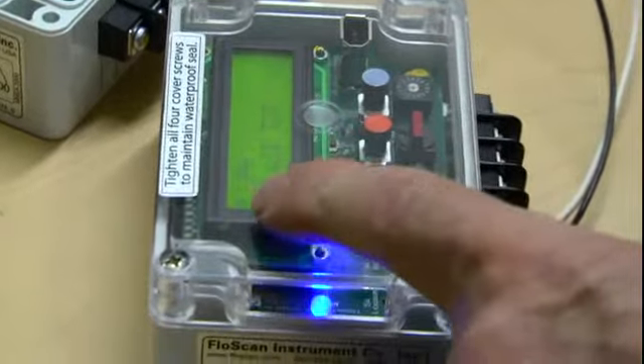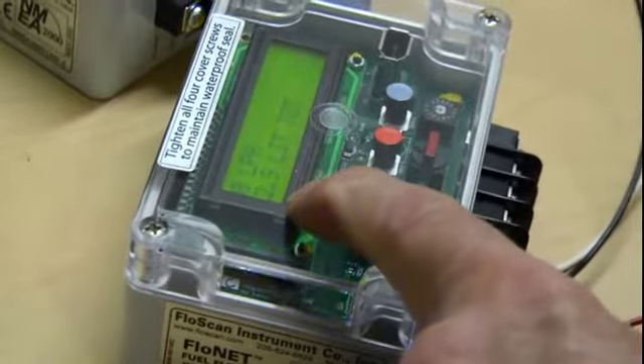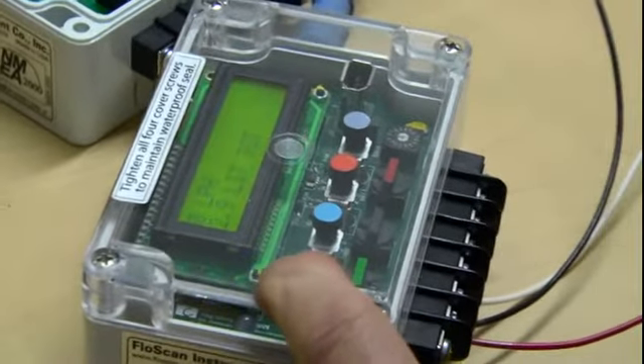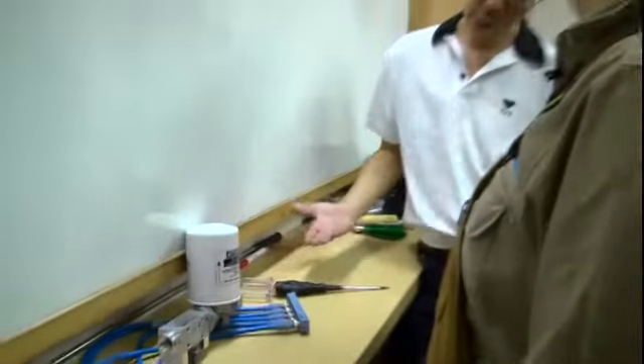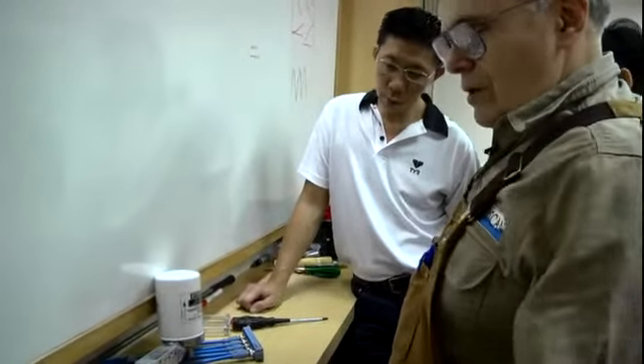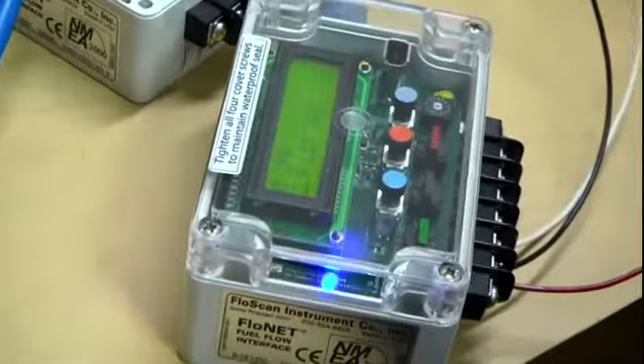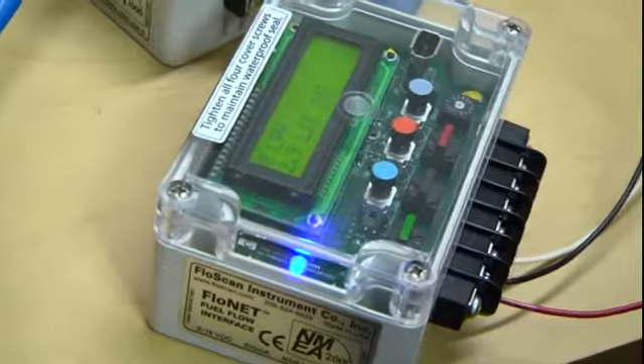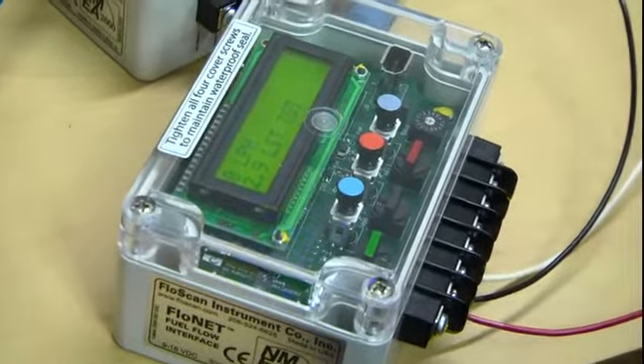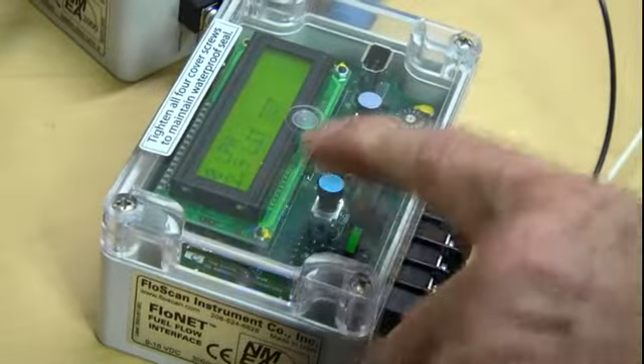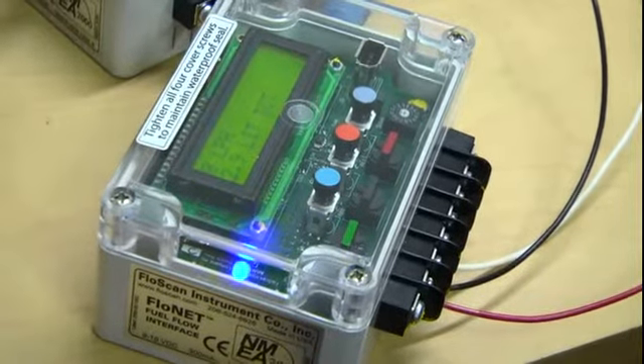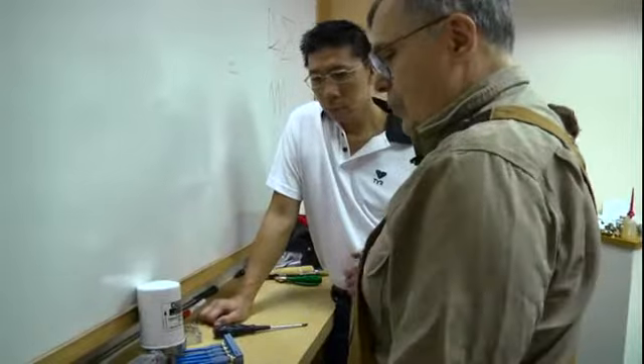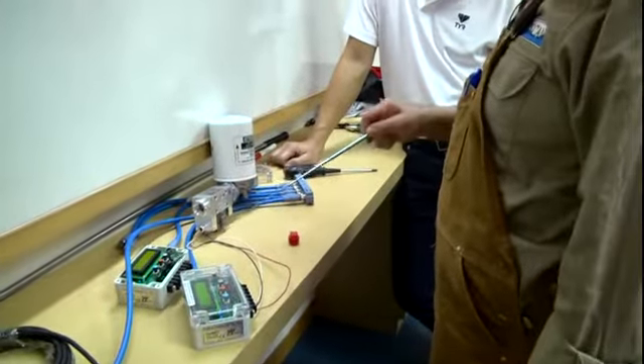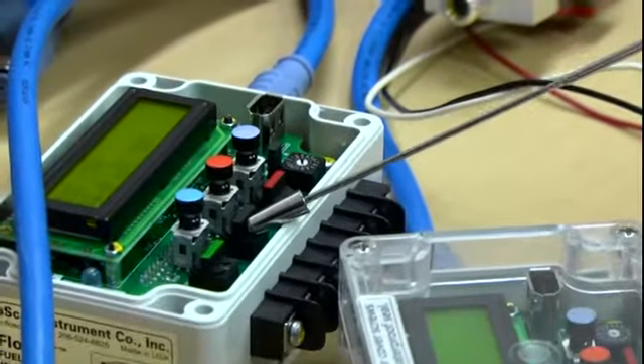See, if we can get a steady liter per hour reading, whatever it is, then we can do the idle consumption adjustment, and then we can do the totalizer calibration. I'll show you how to do it. So with this fan blowing, how much are we getting? Well, I want to see anything from 5 liters an hour, 10, 15 liters an hour, something like that. It doesn't have to be perfect. But initially, maybe we can run it faster so we build up the totalizer quite a bit. Then we can back the fan off, and we can do the two calibrations that are required. The idle consumption adjustment is done with the red switch, and the totalizer calibration is done with the black switch. To make it easier: idle consumption adjustment, red switch; totalizer calibration, black switch.